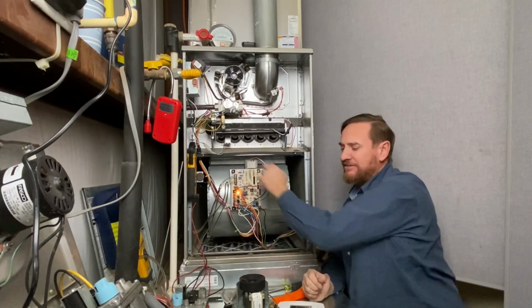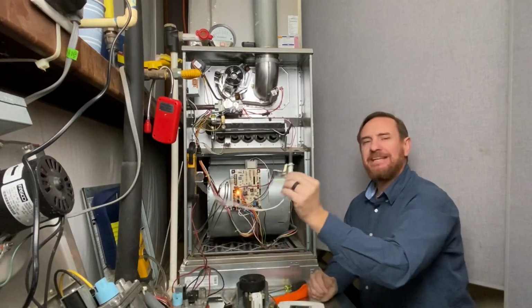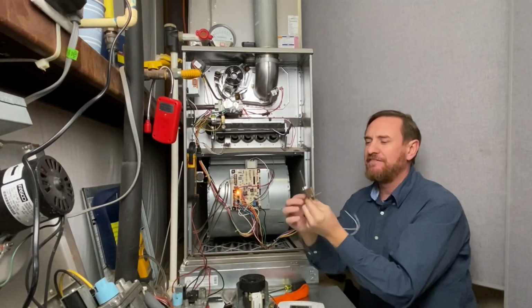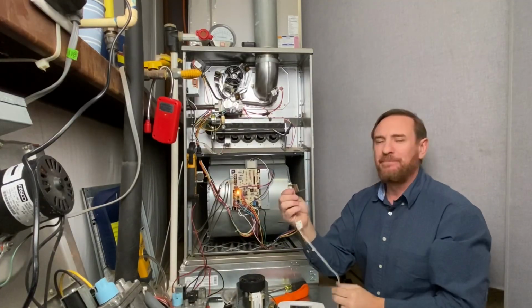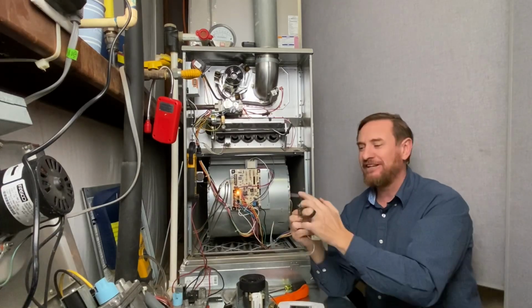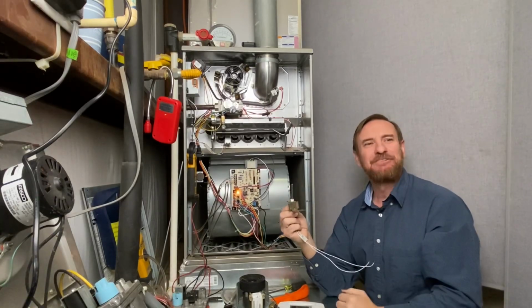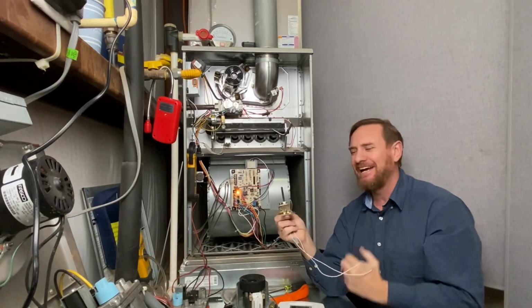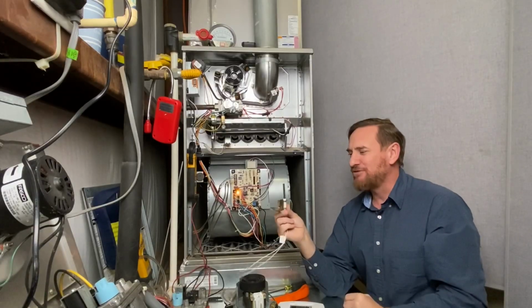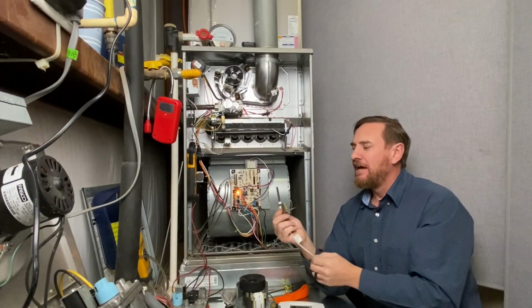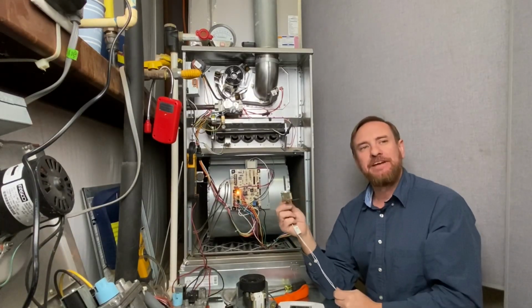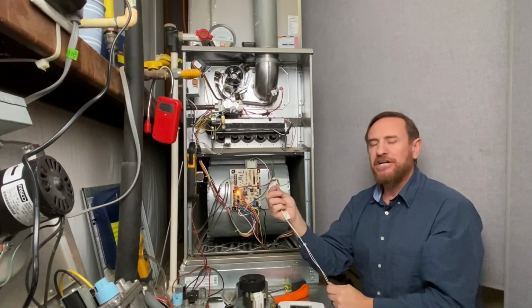it then energizes the hot surface igniter. There's many styles of hot surface igniters. I love these newer styles because they're built a lot better. The old ones, if you tried touching it like that, you're done. They would crack. You could look at them wrong and they would break. These new ones, the silicon nitrides, are really nice. They're heavy duty. They last a whole lot longer, but this is one of your big fail points. This is probably your biggest replaced part.